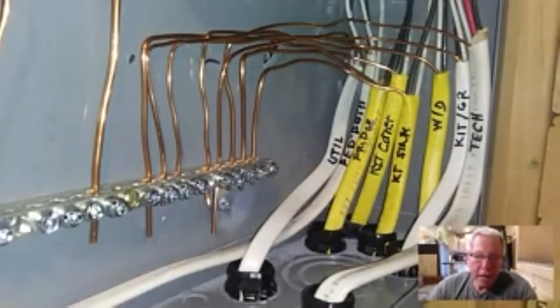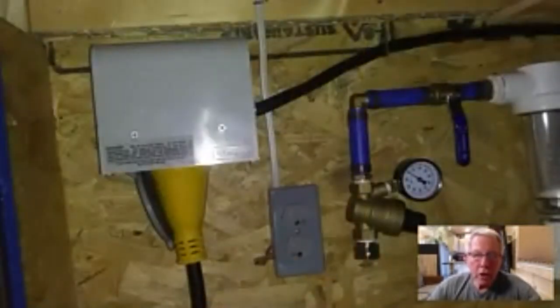The electrical panel - everything's marked and tagged, grounded, everything's done to code. I chose to use combination arc fault, ground fault circuit breakers for every circuit in the house, with a whole house surge protector. So again, a lot of extra money, but no matter what code requirement there is in individual areas, this would pass.